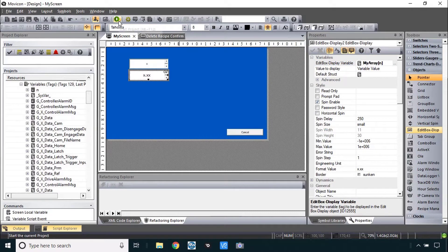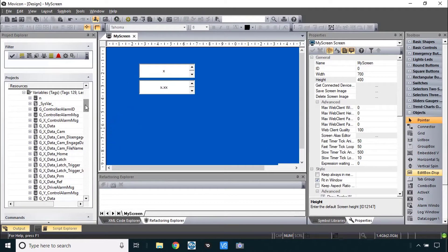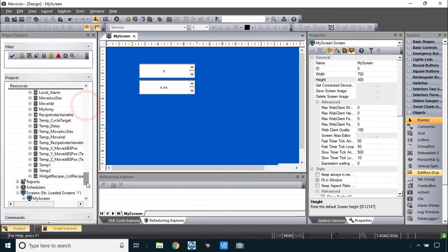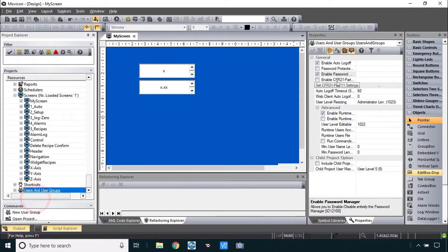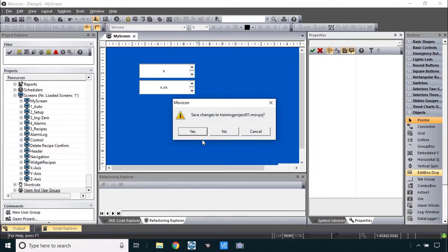Now let's run this. A little trick: you can hold down the run button and choose 'run screen' — that's different from start project. Run screen just runs this screen and does not require communications to be working; it starts up a little quicker too. Before using that, I should remove password protection on my project. Under users and user groups, enable password manager, I'll just deselect that. And now — run screen.